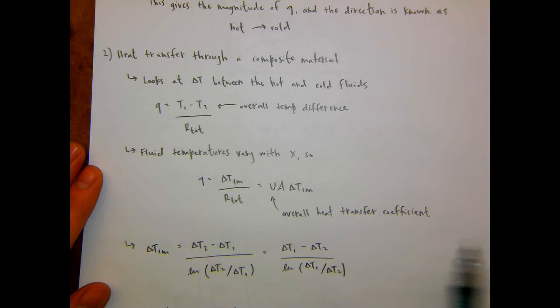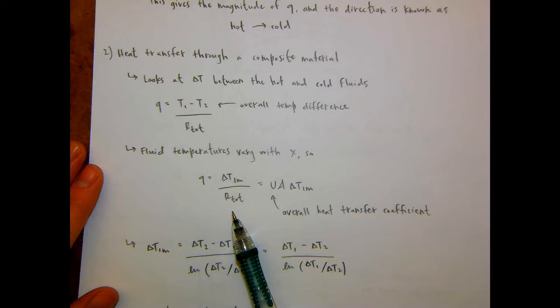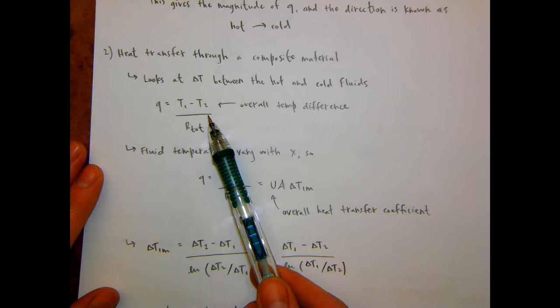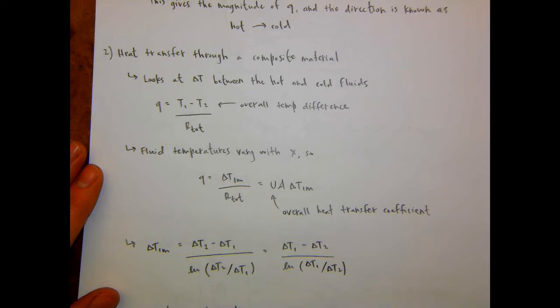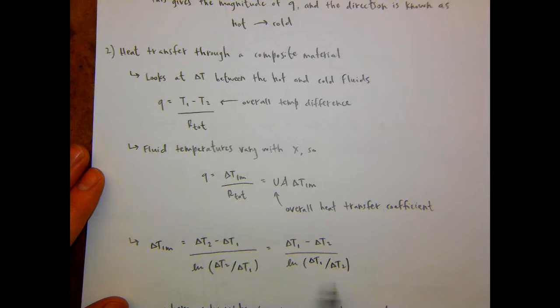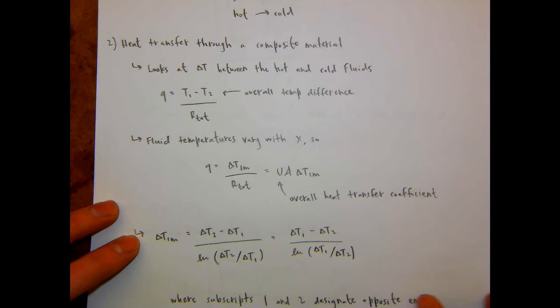You can also use the expression for the composite cylinder equation, where instead of a total T1 minus T2 on top, we have the log mean temperature difference, which is relevant because the temperatures of the fluids are changing in X, and then we have the total thermal resistance on the bottom. The expression for the log mean temperature difference is delta T2 minus delta T1 over log of delta T2 over delta T1.